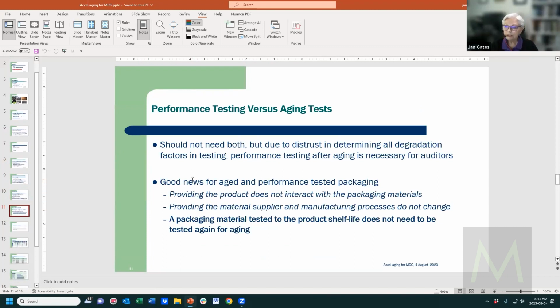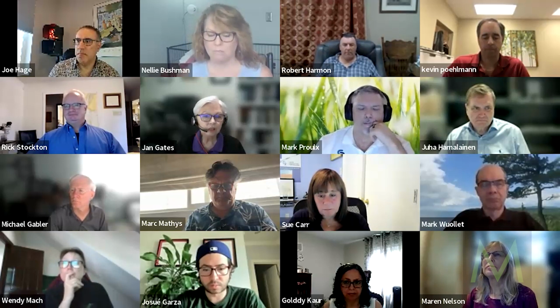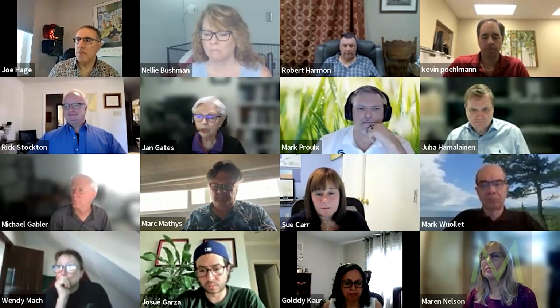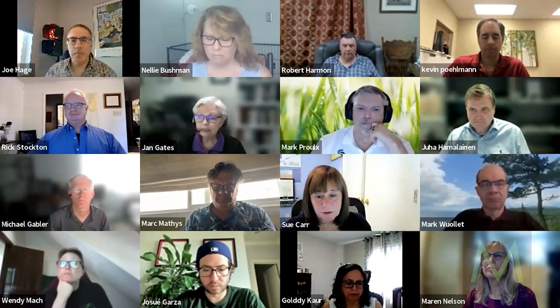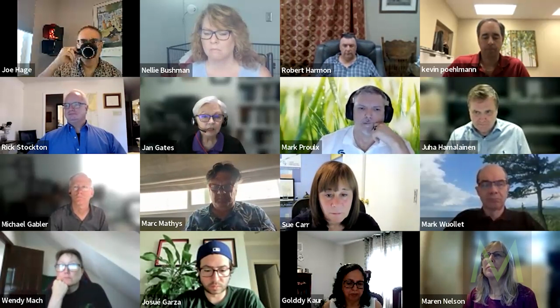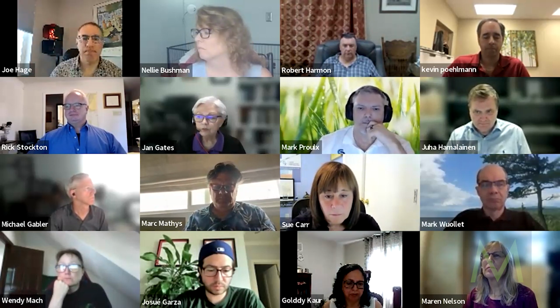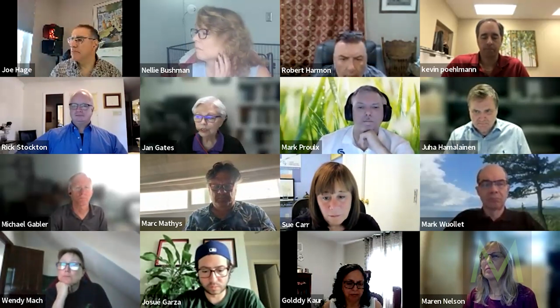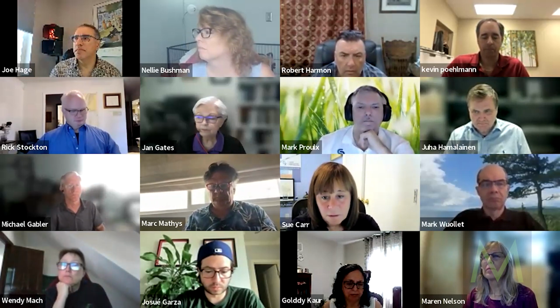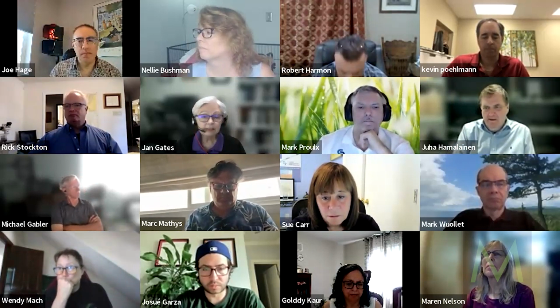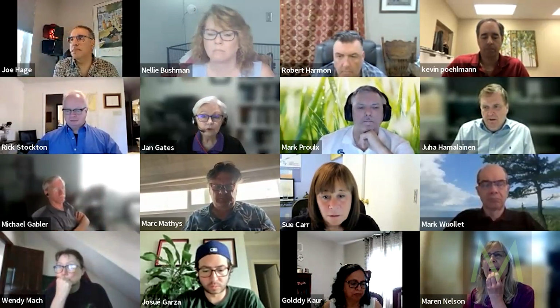One thing that's really nice: you're not supposed to have to do performance testing and aging tests together, but because there's a lot of distrust on you knowing all your degradation factors and testing, they make you do performance testing. Performance testing is actually like shipping studies to make sure that the shock and vibration doesn't affect your product. The best news, at least for packaging, is once you do your aging tests and get them all done, you never have to do it again, as long as the product's not interacting with the materials and you don't change your manufacturing processes and your material suppliers. So that's nice. Once you do it, you don't have to do it again.